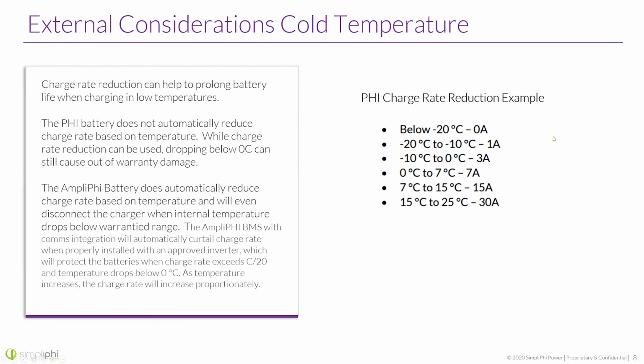But the SimpliPhi can actually do this on its own. If it sees it go below or to 0, it can ramp down the charge rate before just disconnecting the charger, so it gives a little leeway. If we hit below 0, it'll try to reduce the charge rate, then it will disconnect if it still is getting lower. So that's a nice feature of the SimpliPhi, and it's a great battery when you have cold weather restrictions.